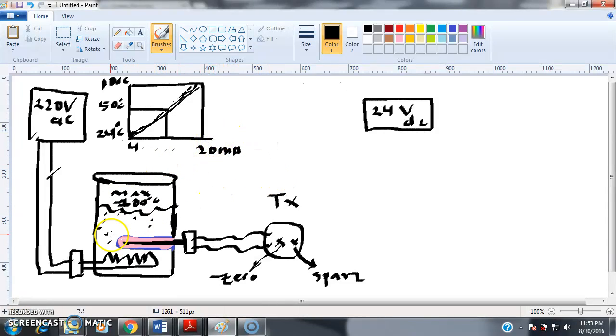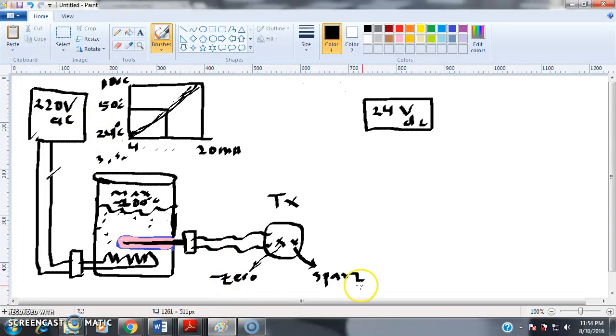Let's say the temperature is at 24 degrees and the RTD is giving us 3.5 milliamps. Before we start measuring, we need to calibrate the instrument. We adjust the Zero to bring 3.5 up to 4 milliamps. Then when the temperature is at maximum and you are reading 19.4 milliamps instead of 20, you adjust the Span to bring it to 20 milliamps. That's the purpose of the Zero and Span.